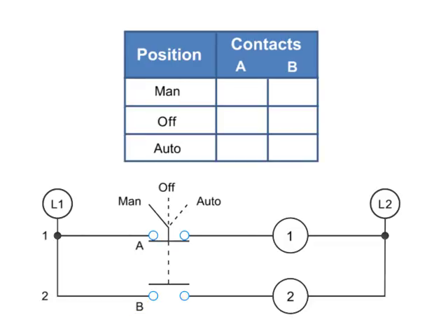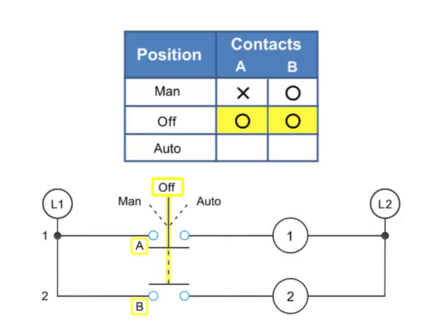In this illustration of a three-position selector switch, a third row is added to the truth table, so we now have a manual position, an OFF position, and an AUTO. Thus, in the MAN position, A is X or closed and B is O or open. At the OFF position, both A and B are O or open. With the selector switch set to AUTO, contact A is O or open and B is X or closed.